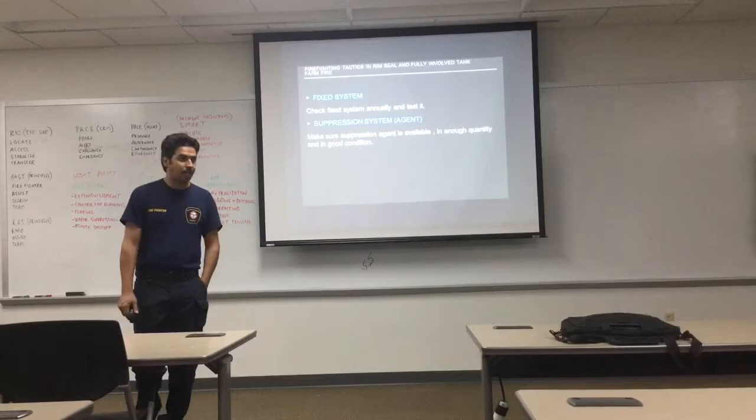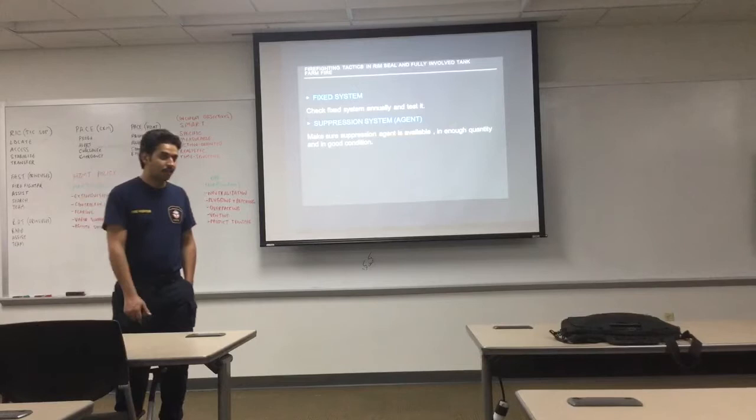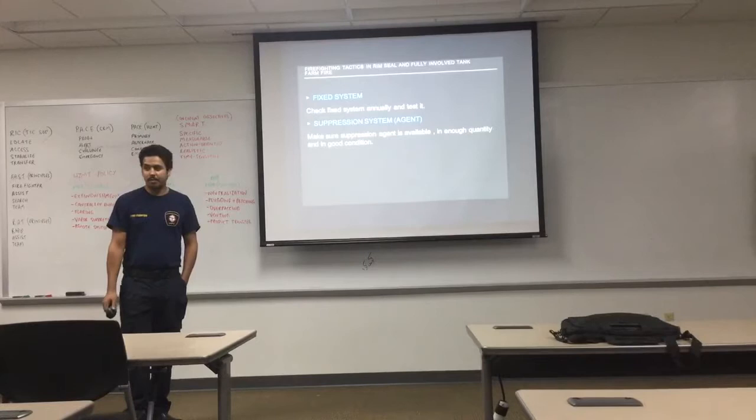Sometimes there is a lack of information from the operator working in the tank — we should have clear information about the contents and quantity of the tank. Fixed systems should be checked and tested annually to ensure they work properly when needed. Suppression agents must be available in sufficient quantity and good condition — resources like foam and water should be calculated based on the quantity of liquid in the tank to ensure enough agent is available when a fire occurs.